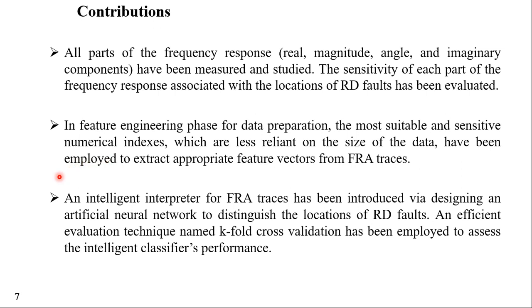And also we have designed an intelligent interpreter for FRA traces, and we have used artificial neural networks to distinguish locations of RD faults. An efficient evaluation of the classification with k-fold cross-validation has been done.